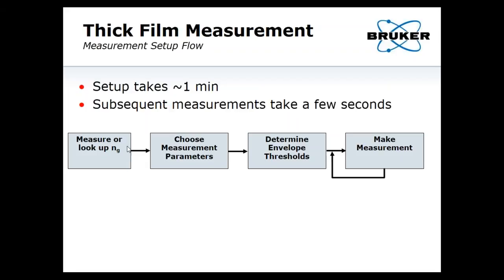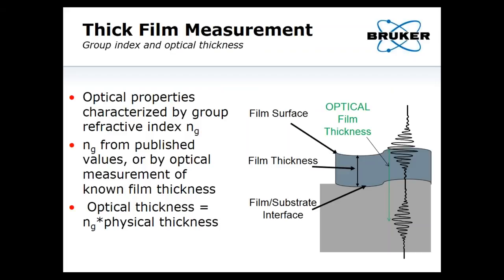First you need to know the group refractive index. Then you set up the measurement the same way you would a normal VSI measurement. Then you define some envelope thresholds that set the signal and noise for both the top surface of the film and the bottom buried interface. Once that's done, it's one and done per sample type. You can just loop these measurements and take as many as you'd like, and you can automate this to sample a whole wafer or a number of devices.